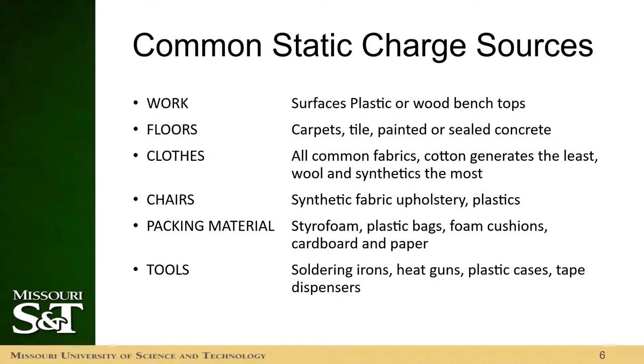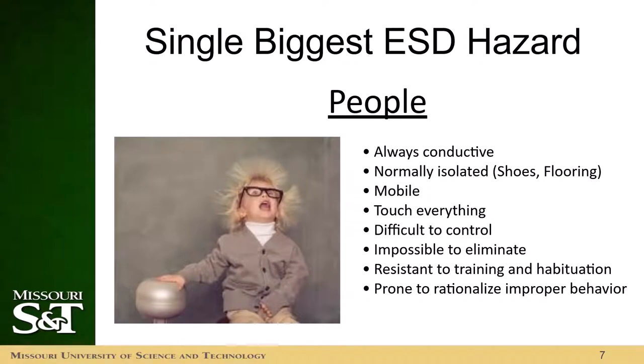Here are some common static charge sources — things such as work surfaces, floors, clothes, chairs, packing material, and tools. All of these are things you might see in the lab, and it's important to keep an eye on them because these are insulators and charges can build up on them if you're not careful. Another thing also in the lab is people, who are the single biggest ESD hazard. They're always conductive, isolated by shoes, mobile, and touch everything. A lot of these risks can be mitigated by just being careful and paying attention to what you're doing.